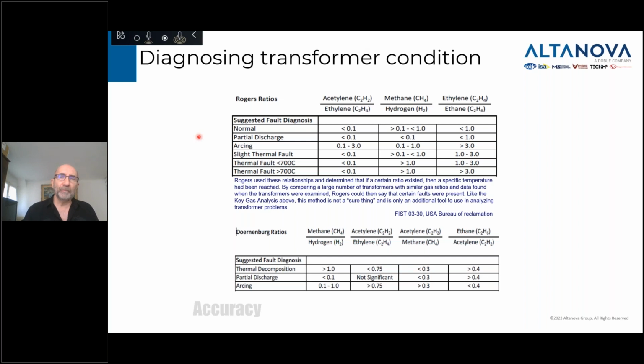Often people will compare the diagnostic of each of those three. The past experience from a lot of customers is that if those three tools, the Rogers ratio, the IEC, and the Duval triangle, arrive at the same diagnostic conclusion, you have a very high probability that this is the right fault being developed in your transformer. Usually it's around 90%; I've heard numbers between 90 and 95% if all three tools come to the same diagnostic. So it's a very strong diagnostic that can help you find out what's going on in your transformer, as long as the data is also very accurate.